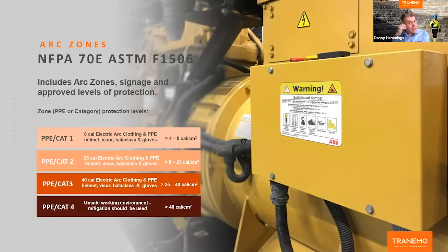The NFPA 70E American guidance also introduces what's called arc protection zones, or sometimes called PPE categories, or just category 1, 2, 3, or 4. And this is designed to create the concept of safe working environments where there is an arc flash risk rated 1 to 4 based on levels of incident energy. Most areas we would see here would be within PPE category 2, which is the 8 to 25 cal risk.